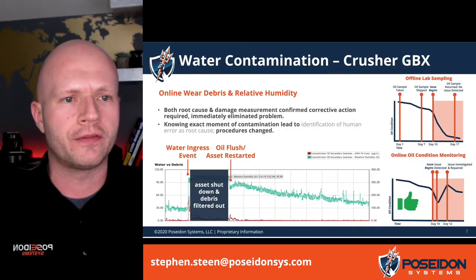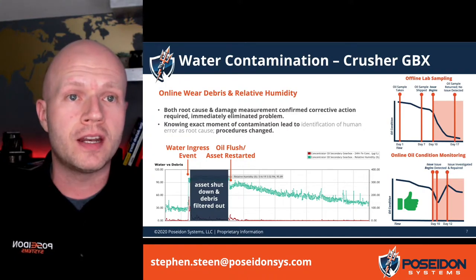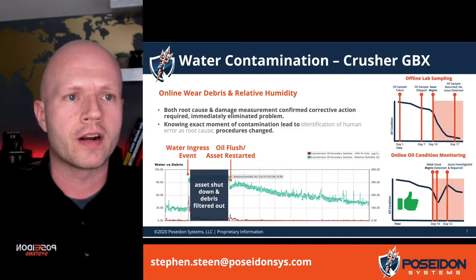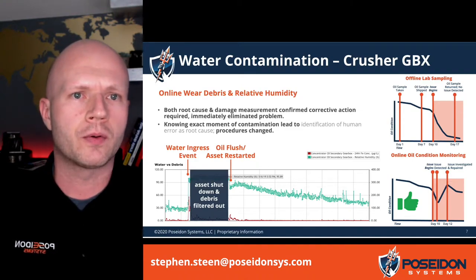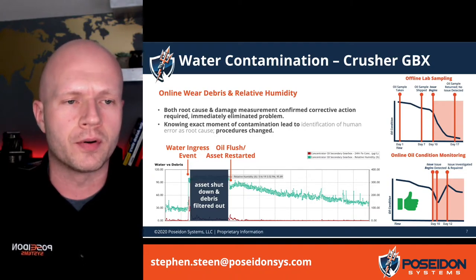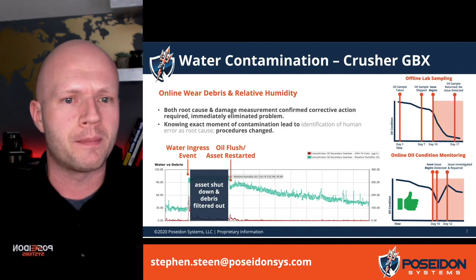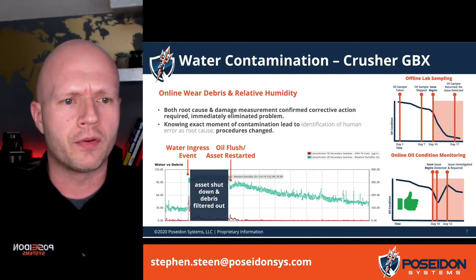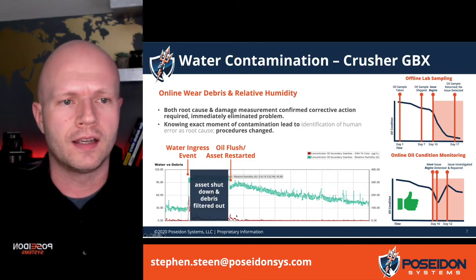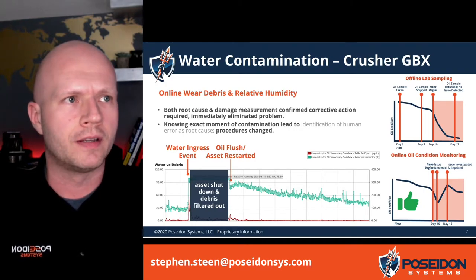Using online relative humidity as an example — this is a good one where an event of water contamination was caught immediately. The damage was actually measured from the wear debris sensor, directly measuring how much metal was released when the water got in. Because of that, we were able to see both the root cause and the damage measure. We were able to confirm the corrective action: they shut it down, filtered out the debris and the water, and returned the relative humidity back to the normal 30% after doing an oil flush. This is an example where they probably would have been a month or two before they may have even drawn a sample and found a fault — and it would have been operating with quite a lot of water and generating that debris, probably leading to a catastrophic failure. In this case, a crushing gearbox.